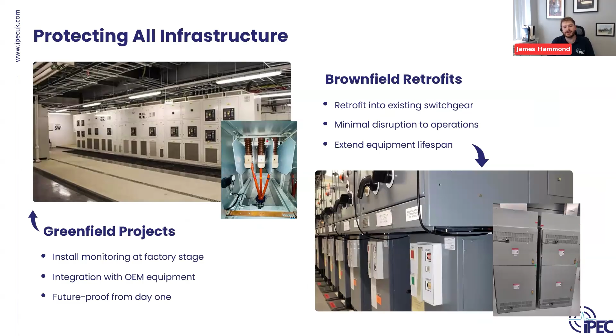Got some interesting points there, things that I come across quite a bit. One of the points is, a client that I'm supporting at the moment for a switchgear installation has opted not to go with the permanently monitored sensors because it's a new board - that's their choice, but based on the criticality it should be formed a risk assessment. Is it critical? Who's working around it? That sort of stuff, then a decision made from there, because it's so much easier to put on in the panel shop. That's my point - from a design side, it's better to put on when it's been built up rather than 5 years, 10 years down the line when it's actually in operations and you've got to take individual feeds down at a time, plan the downtime for retrofitting. It's more costly, takes more risk, takes longer, that sort of stuff. But yeah, it's a really good point, that comes up quite a lot. Yeah, definitely.